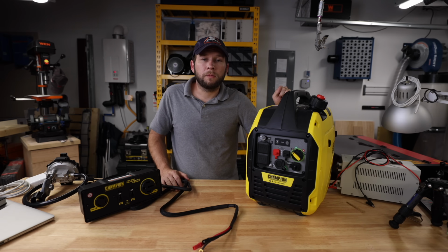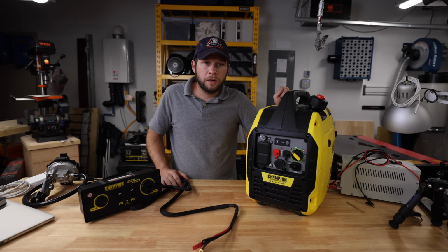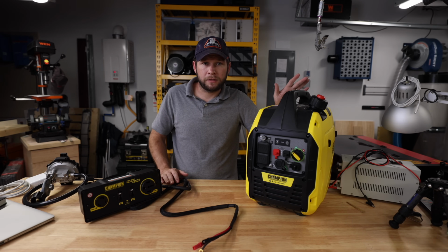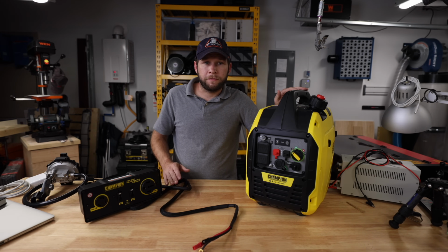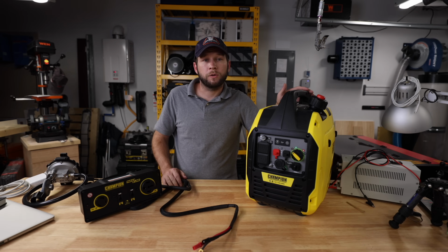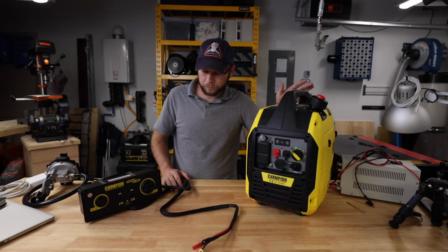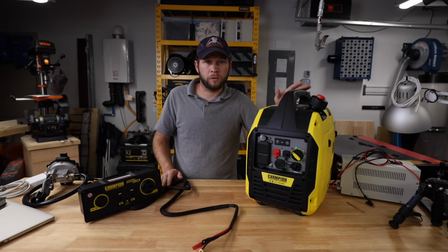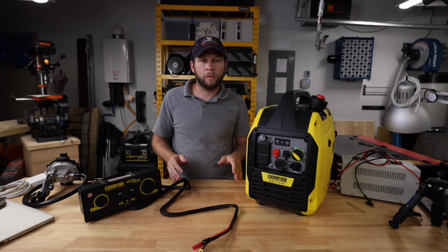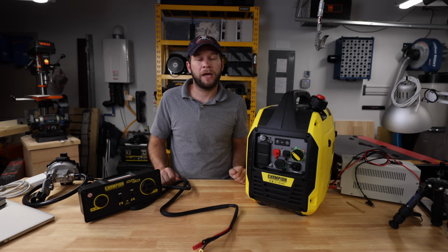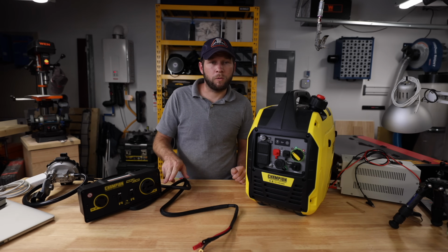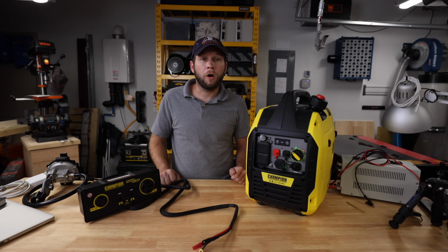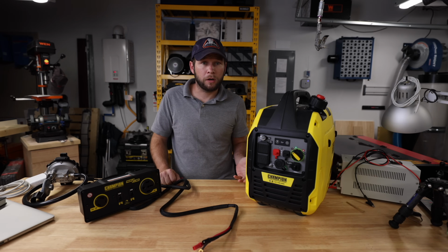Where this comes into a problem is when you tie it into your house. Now, when you tie something like this into your house through a generator inlet, something like that on the outside, and that's connected with a 50 amp generator inlet or a 30 amp 240 volt generator inlet, one of those, L1, L2, so the red and the black usually, those are going to different bus bars in your main panel, which have the different breakers on them. So by splitting the power to L1 and L2 and having that 120 volts, all of your breakers in the panel do see power.